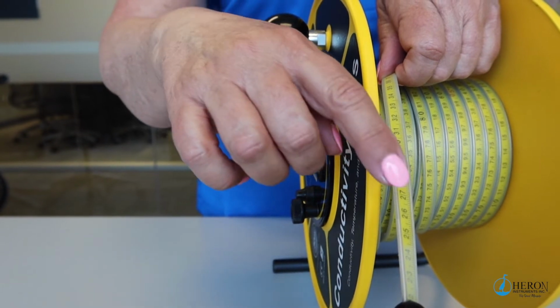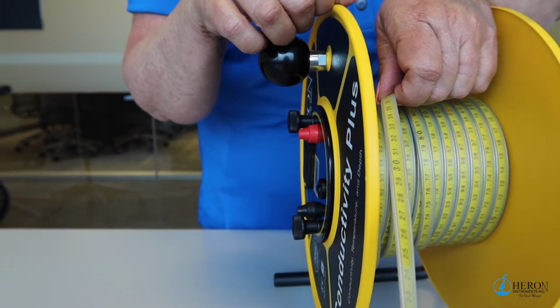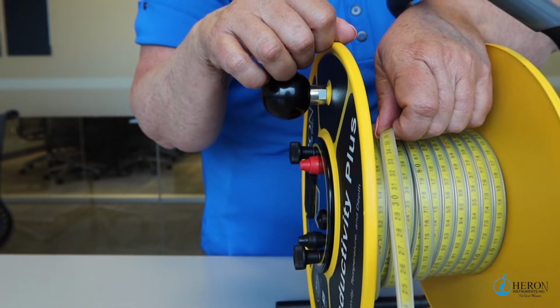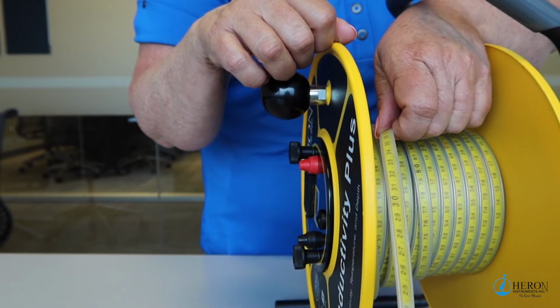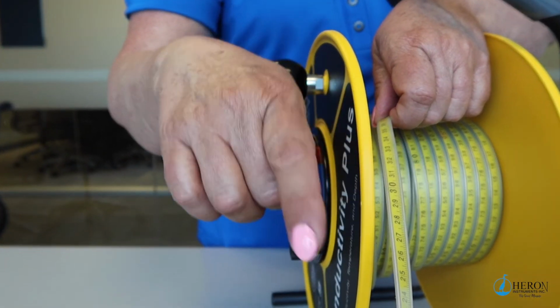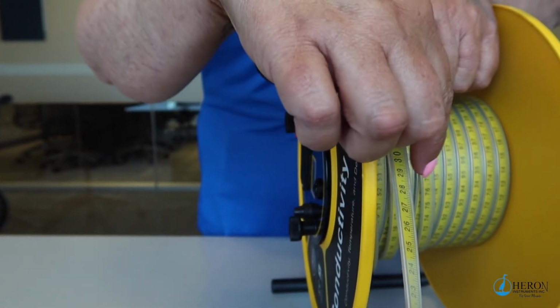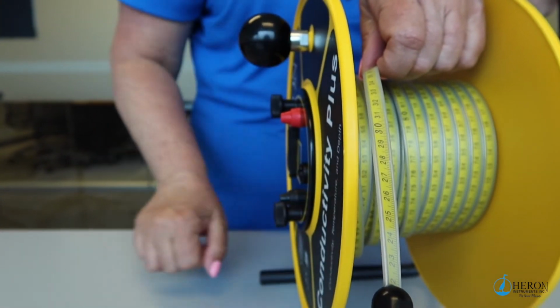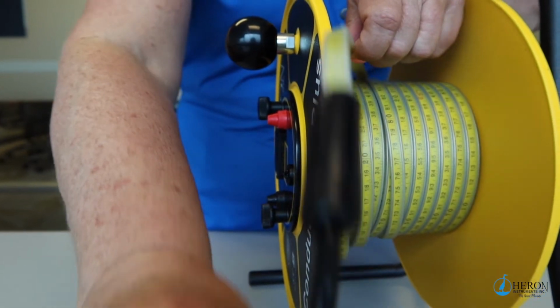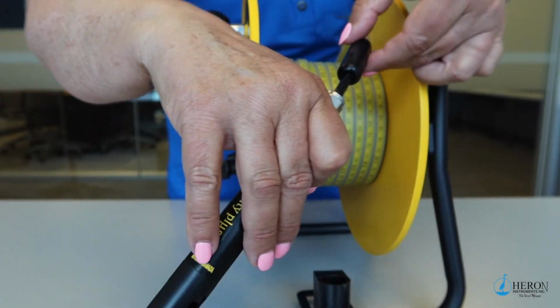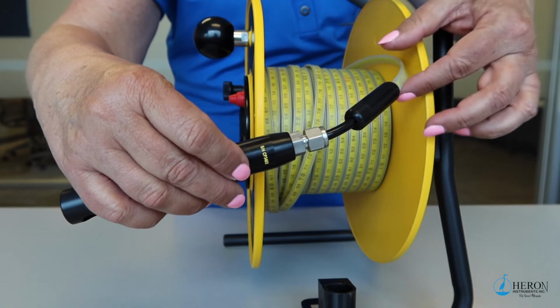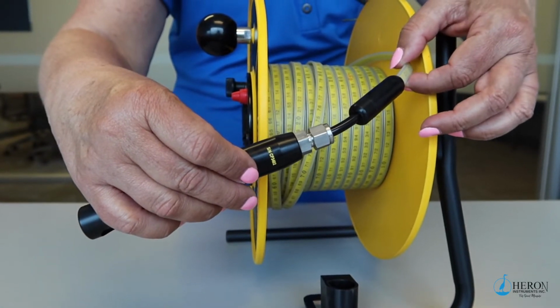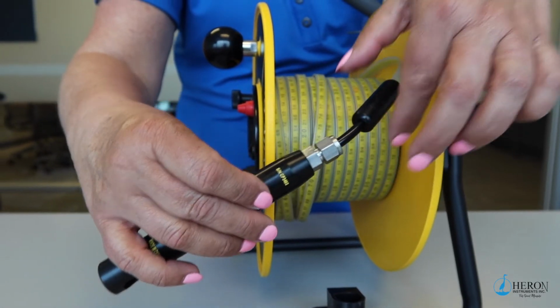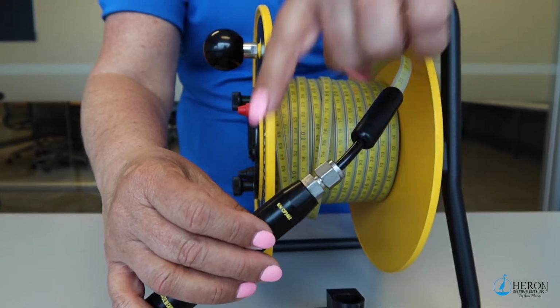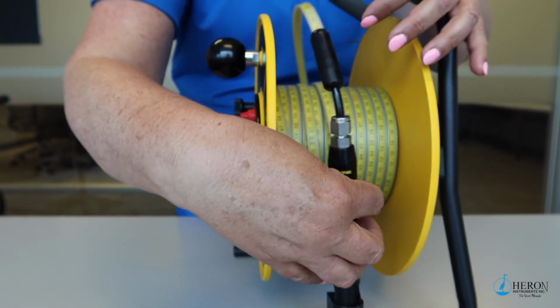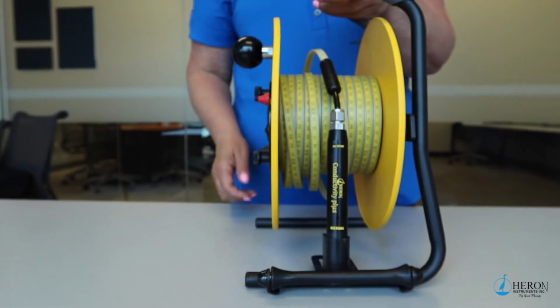The tape comes in either metric or imperial markings. The imperial markings are in an engineering scale. The tape has a dog bone profile, meaning that it's rounded on either side and flat in the center, which helps eliminate sticking to the side of the casing. There is a shear pin style linkage above the probe, which will break away if your probe gets stuck in the well. Better to save your expensive tape and lose your inexpensive probe, both of which are modular and replaceable as shown in our parts list.